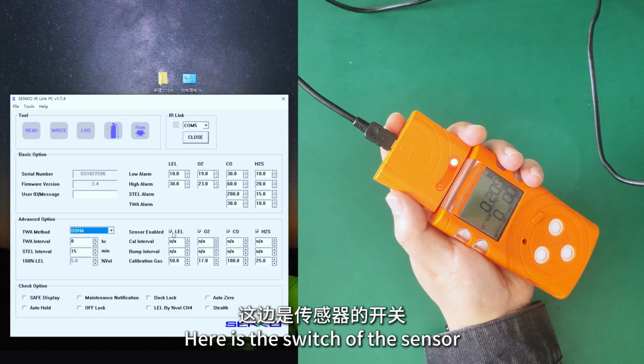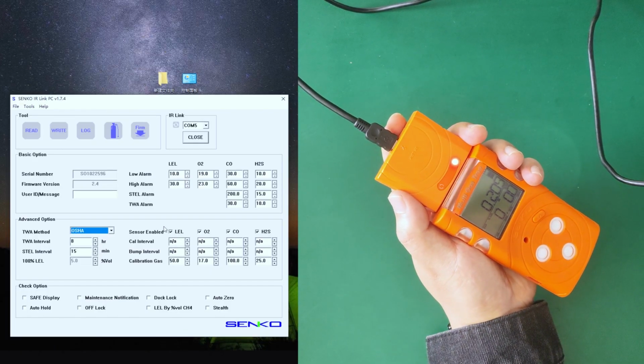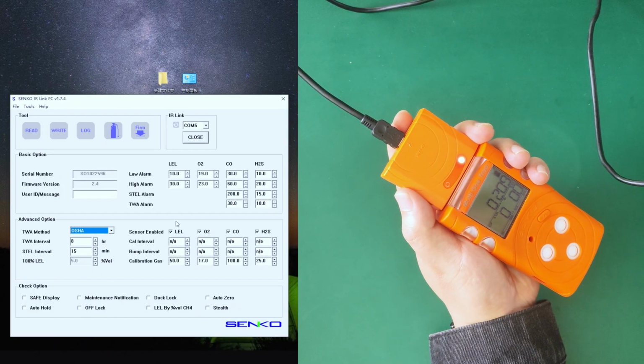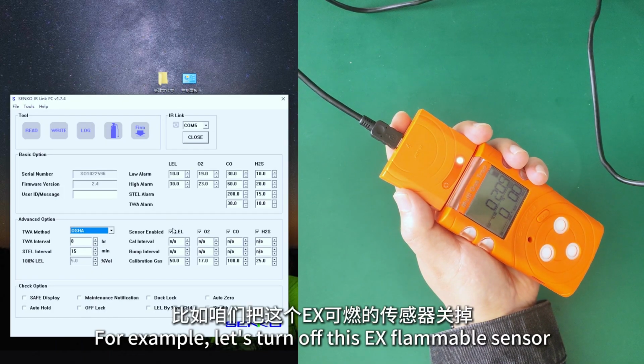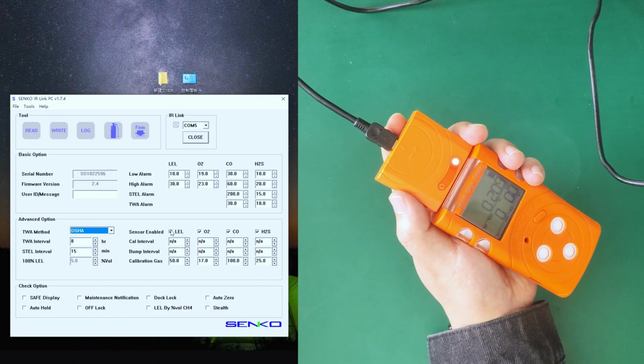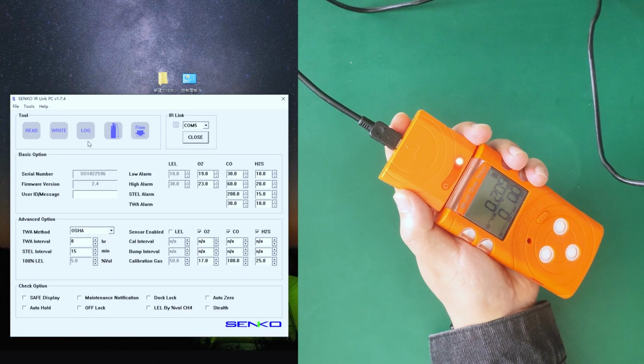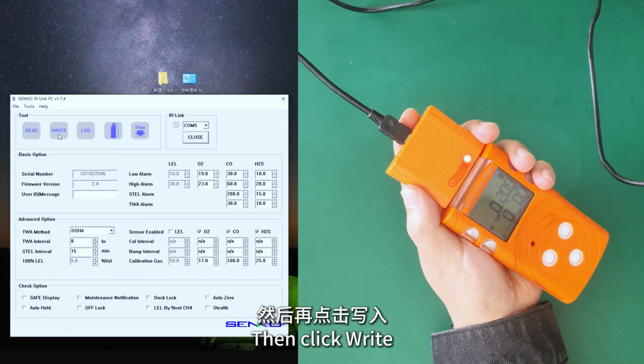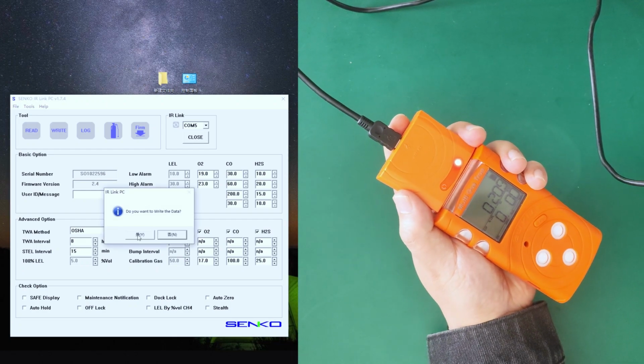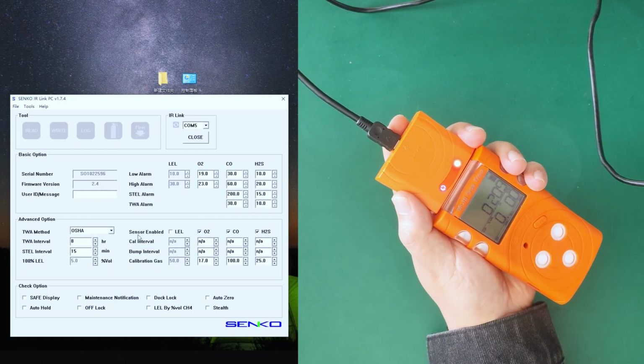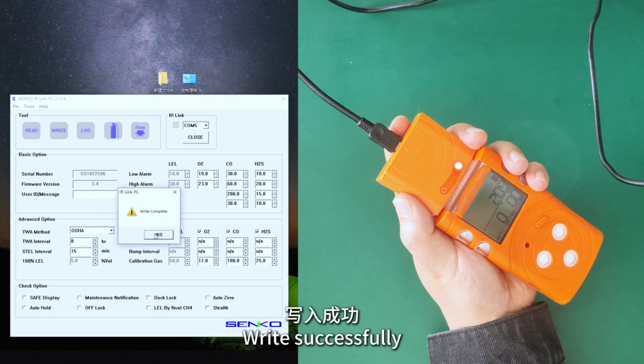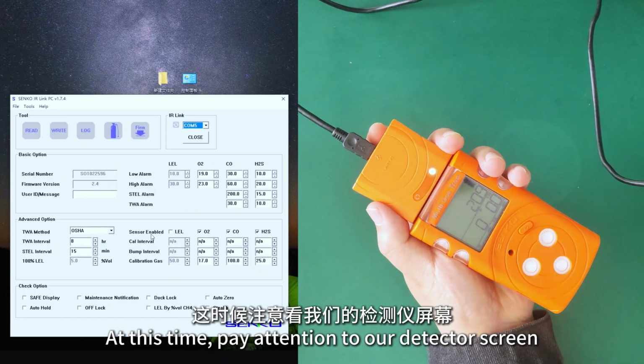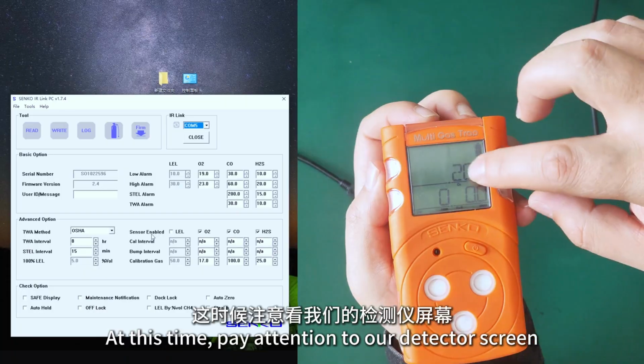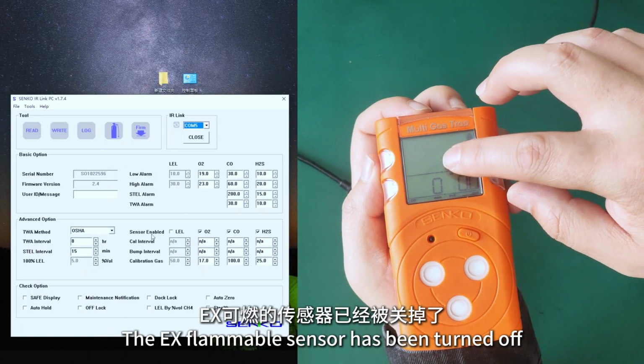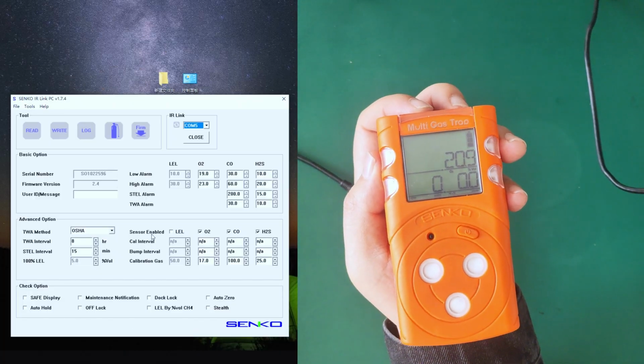Here is the switch of the sensor. You can block a certain sensor here. For example, let's turn off this flammable sensor. Click the small box to untick. Then click Write. Click Yes. Write successfully. At this time, pay attention to our detector screen. The flammable sensor has been turned off.